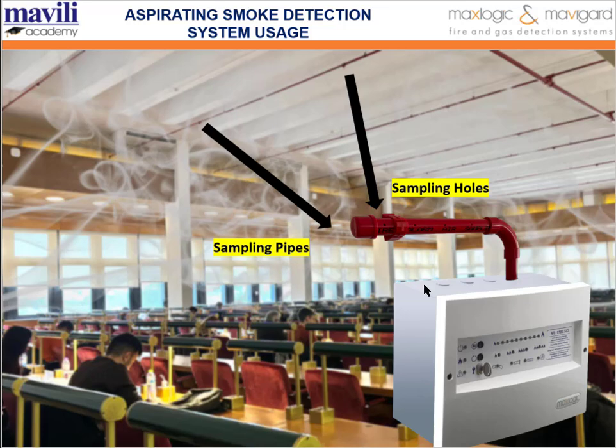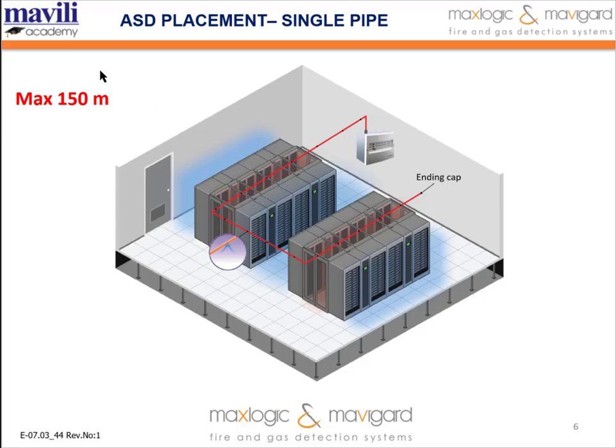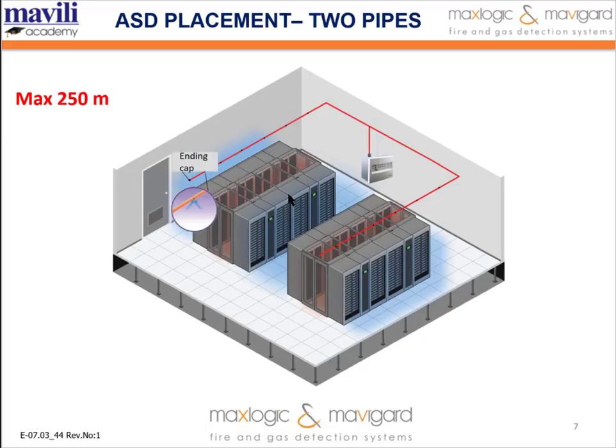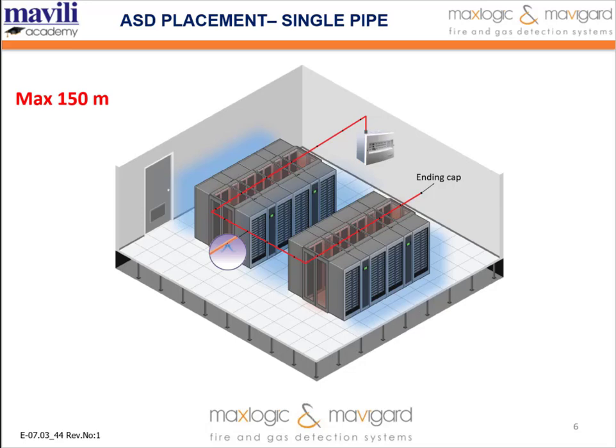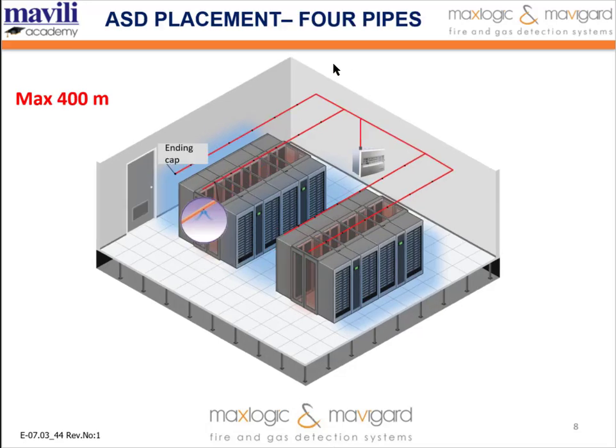So why is it preferred in libraries or data centers? It provides very early detection, protects critical areas, and is effective in areas with high ceilings. These are the most important three. Now let's look at the placement of the aspirating smoke detector. We can use one single pipe, placed like this, with a maximum of 150 meters. The other one is two pipes. We can use a T connection apparatus to divide it into two pipes, and we should use ending caps on both of these pipes. And the other one is four pipes.